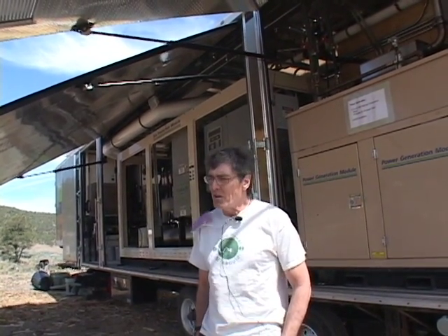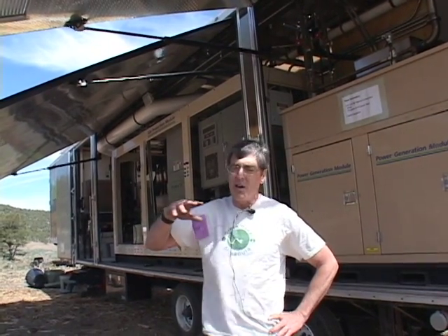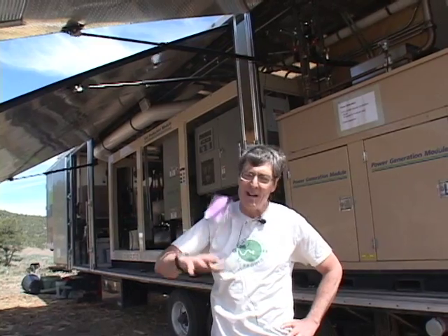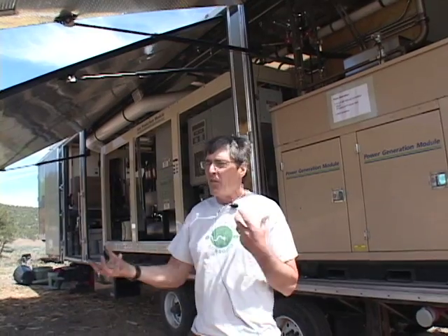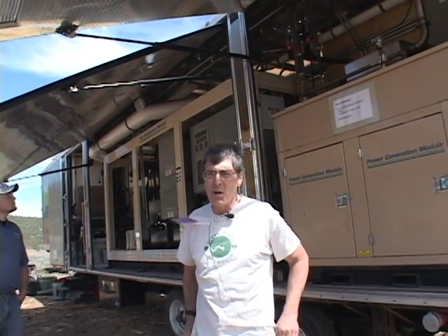It's a difficult load because it's a very dynamic load. This system would prefer to see a nice steady grid load, but we have been able to manage it. We get on sound stages anywhere from a 5 kilowatt usage up to a 15 or 17 and back down. So in order to follow that, you need a fairly flexible, robust generator. Sometimes if we have too big of an excursion, it will fall down, but normally we can follow those kind of loads.